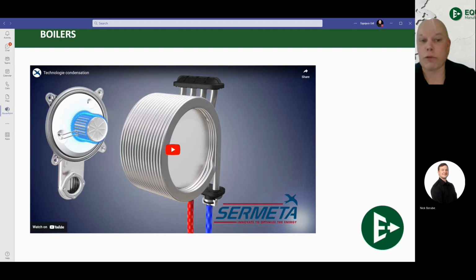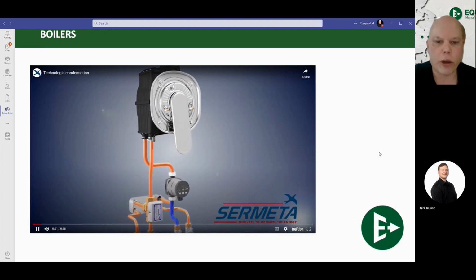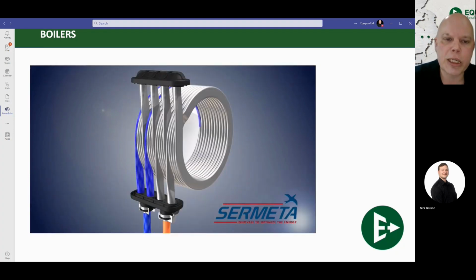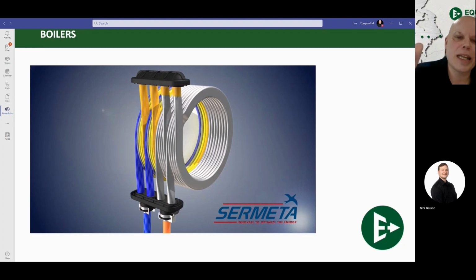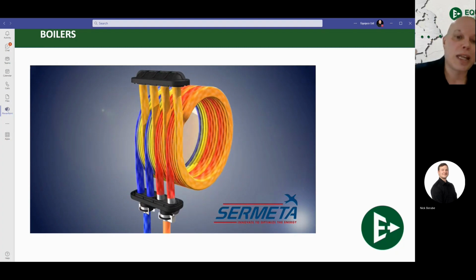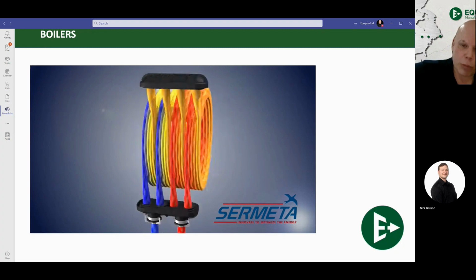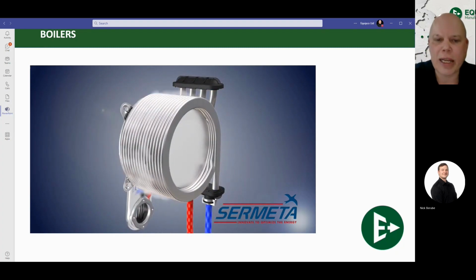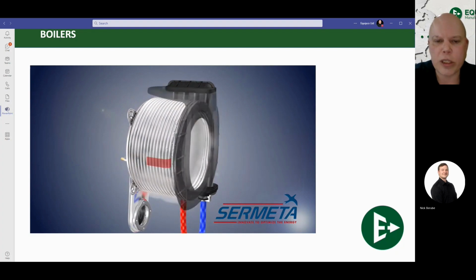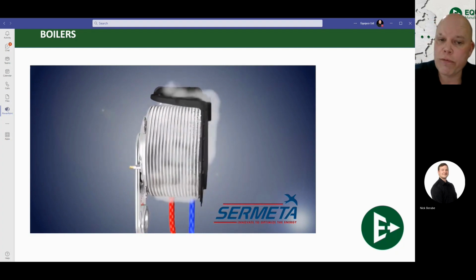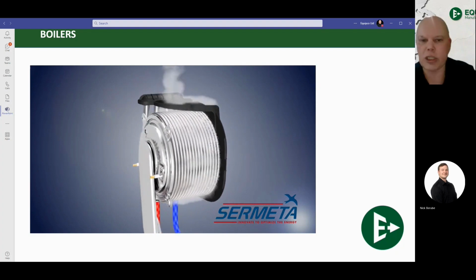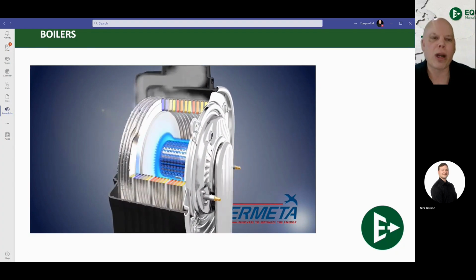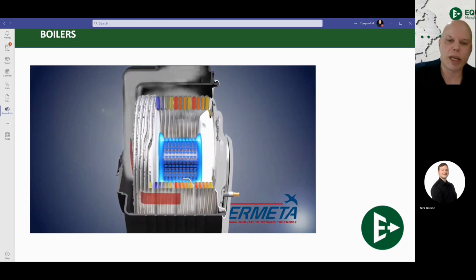The thing about it is that they're extremely easy to take apart and clean, whereas a fire tube is a bit more complex to take apart and clean. So let me walk you through it in a real quick video. Our water is going to be coming up in primary-secondary piping, and it's going to be getting heated through that water tube heat exchanger. Getting heated because our burner, which you're going to see in just a moment, is coming in and blasting that heat, and the heat transfers in between each of these individual coils. So when you're cleaning one of these, it's designed to be cleaned in between these slots. It's not just one big open chamber, it's actually individual lines as we transfer that heat through.